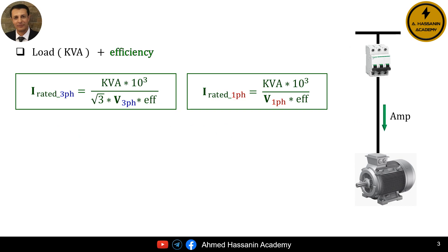The first load unit is the load value in KVA. For dynamic load calculations such as those for motors, we must also consider the motor's efficiency to ensure accurate calculations. For a three-phase dynamic load or three-phase motor, the equation for the rated current of the motor load is the rated power value in KVA multiplied by 10 cubed, divided by the square root of 3, the three-phase rated voltage in volts, and the motor's efficiency.